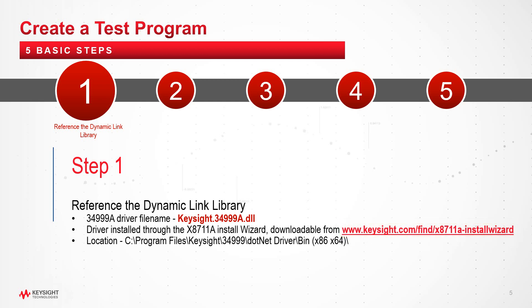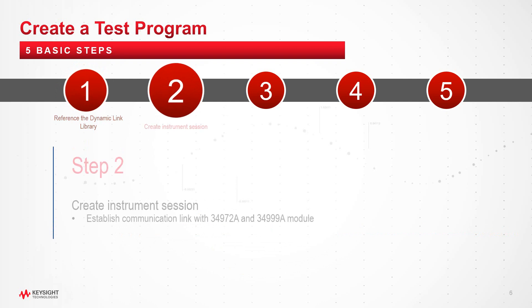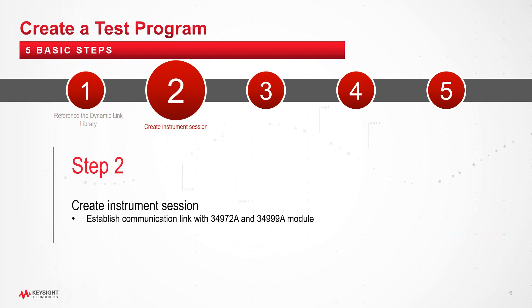Once you have the 34999A driver installed, the driver DLL is located in the directory of your PC as shown on the screen. The program begins with the creation of the instrument session. This is the mandatory step to establish a communication link with the 34972A and 34999A before you could send instructions or receive data from the instrument.